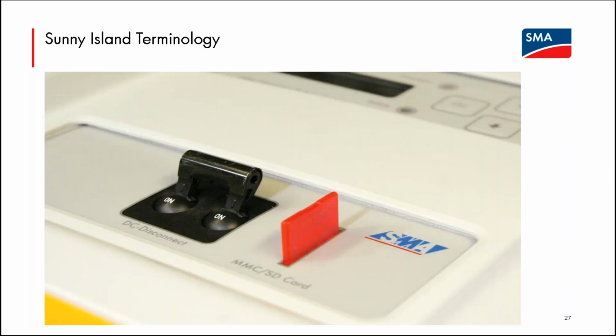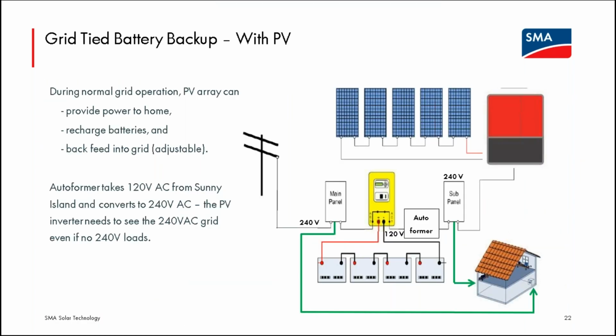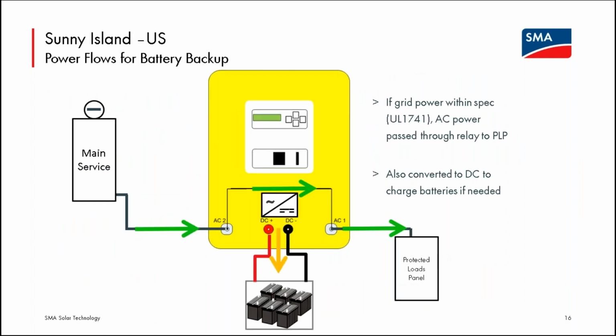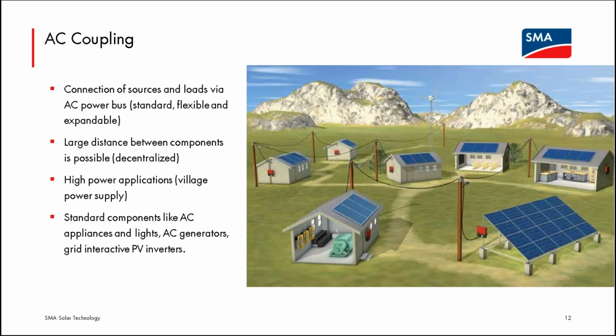Let's see, where's the pretty picture? I'm really backing up here. So there would be, for this scenario, one group of Sunny Islands. So we see the 3 Sunny Islands in the building with the generator. So this would be a 120/208 3-phase AC grid. All of that, the AC waveform here, is controlled by the Sunny Islands until such time as the generator comes in. Those 3 Sunny Islands share that battery bank to the right of the group, and their AC output would provide microgrid power to some set of loads.